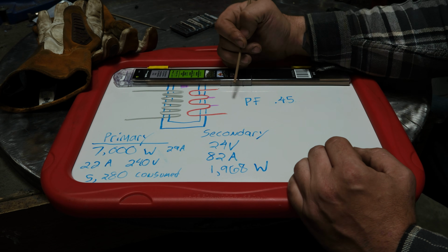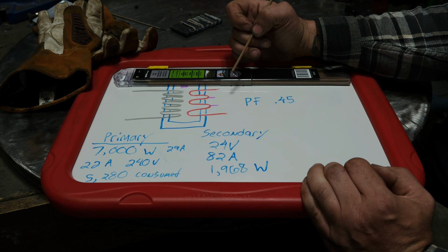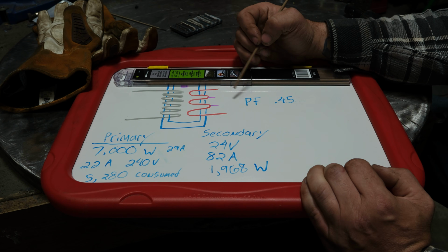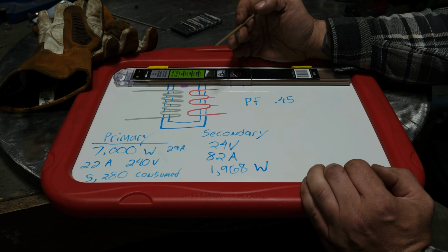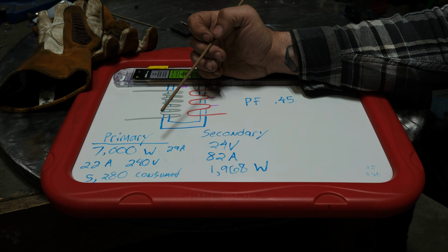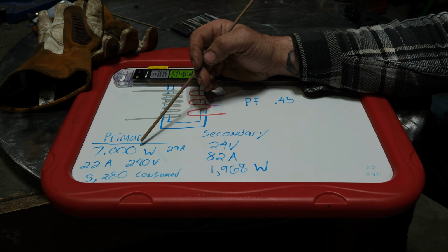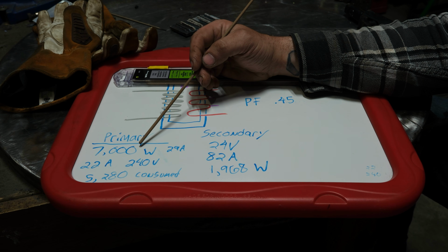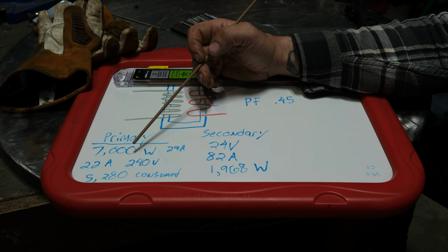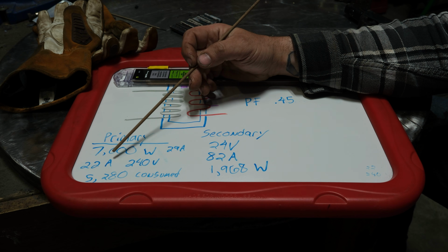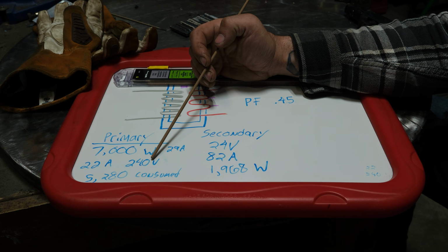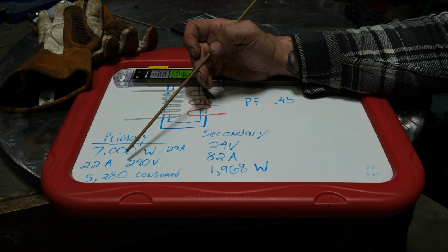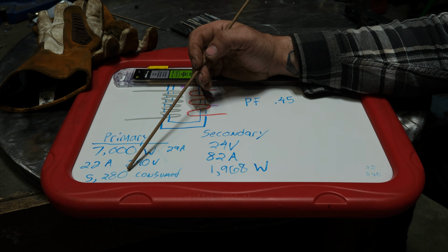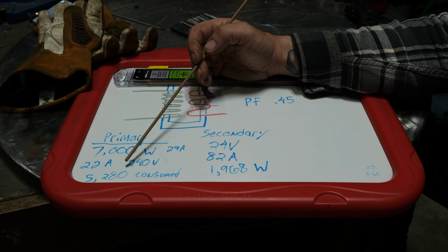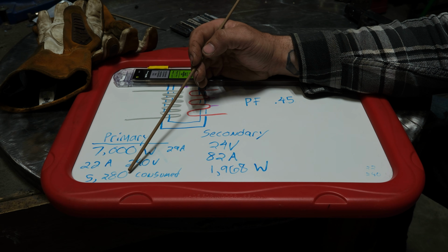Power factor is especially important on generators where a poor power factor is just going to cause breaker trips, even though the device actually doesn't need the amount of power that the breaker's seeing. Anyways, primary side, we're looking at 7,000 watts is what the loading was on the input side. Keep in mind, that's including the reactive power. The actual loading that the device consumed, so only consumption of the device, was 22 amps at 240 volts. That's what it dropped down to while it was operating. So 5,280 watts is actually consumed to weld this 6013 rod that I did. That is a ton of power.